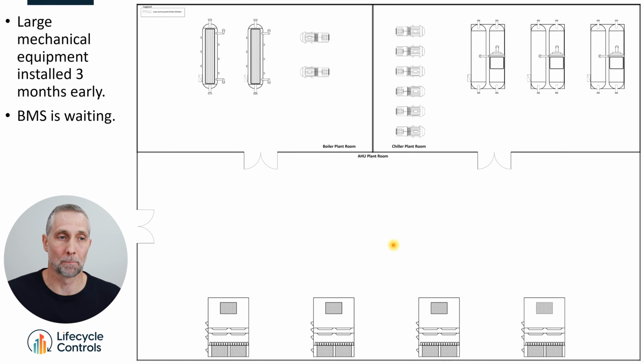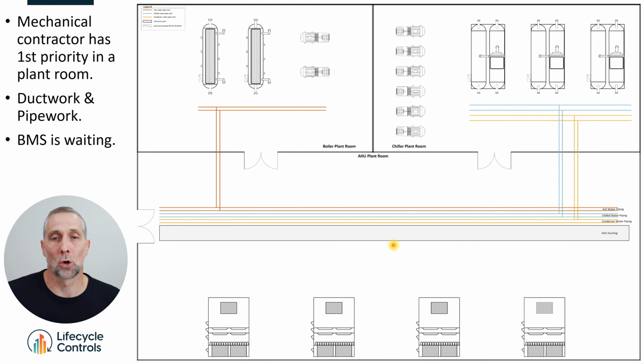You must be used to walking through plant rooms and just seeing air handler units sitting there for months doing nothing. So the first thing that happens is that the mechanical contractor usually has priority in the plant room. So they start installing their heating hot water pipework to the boilers, their chill water pipework and condenser water pipework to the chillers, and they start putting all the air handler unit ducting through the plant rooms, and they'll connect that up to all the air handler units and exhaust fans in different systems.